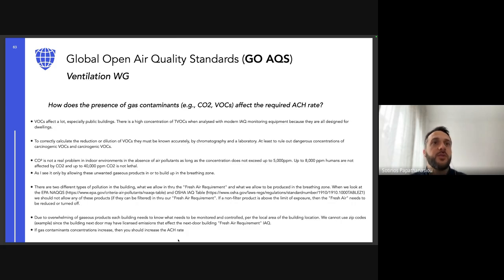There are two different types of pollution in buildings: what we allow in through the fresh air requirement, and what we allow to be produced in the breathing zones. When we look at the EPA NAAQS and the OSHA IAQ tables, we should not allow any of these products, if they can be filtered, in our fresh air requirements. If a non-filtered product is above the limit of exposure, then the fresh air needs to be reduced or turned off.